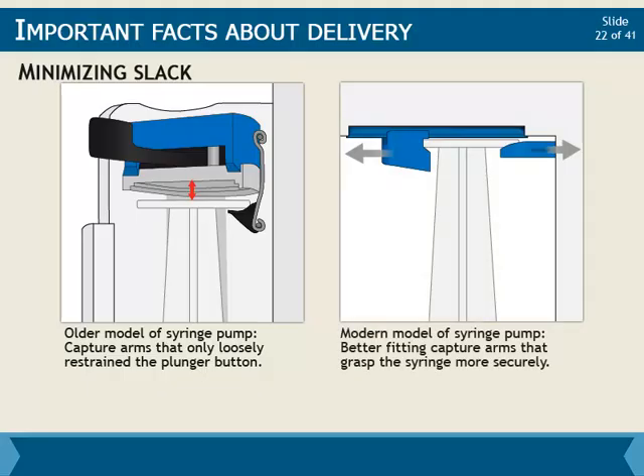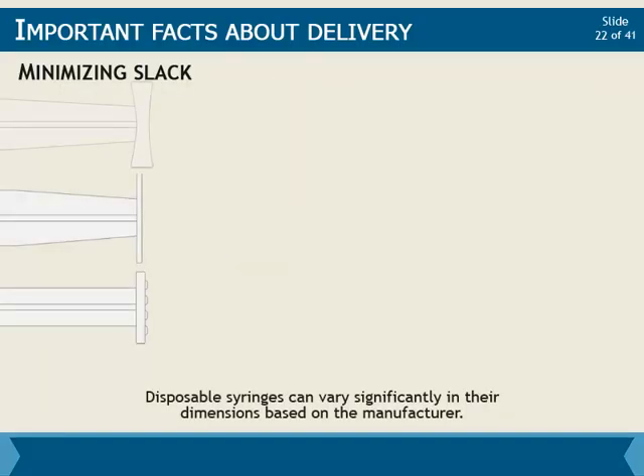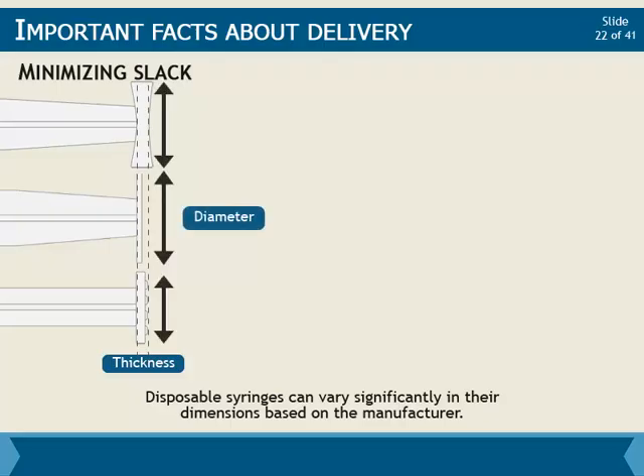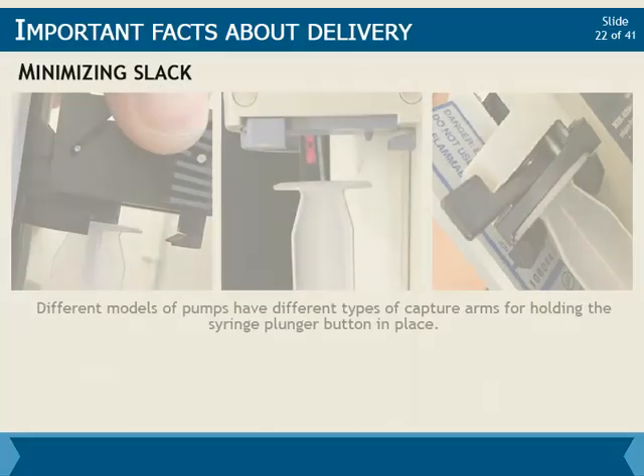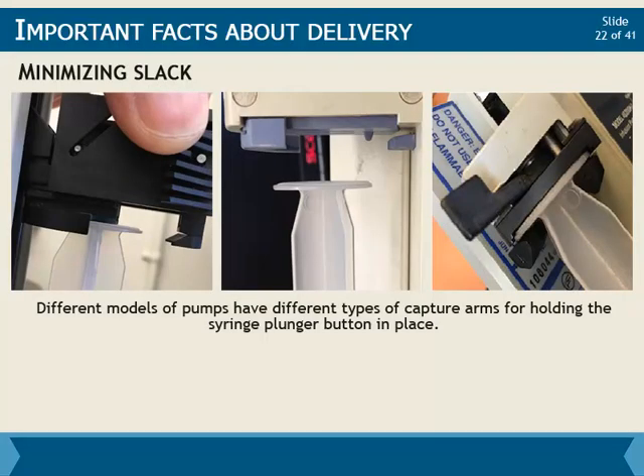Most modern models of syringe pumps have better fitting capture arms that grasp the syringe more securely, minimizing this gap. It is important to recognize, though, that disposable syringes can vary significantly in their dimensions based on the manufacturer, including the size of the plunger button, specifically its thickness and diameter. Furthermore, different models of pumps have different types of capture arms for holding the syringe plunger button in place.